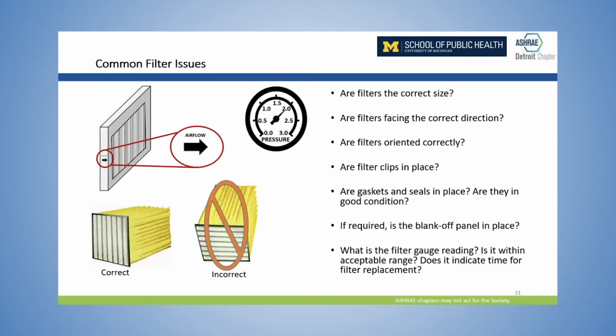And then, you know, sometimes people are well-meaning, but they just go over a little bit. So for example, are the filters installed in the correct direction, right? The bags should be oriented vertically, not horizontally. If you do orient them horizontally, you will end up with possibly reduced airflow and higher pressure drop.